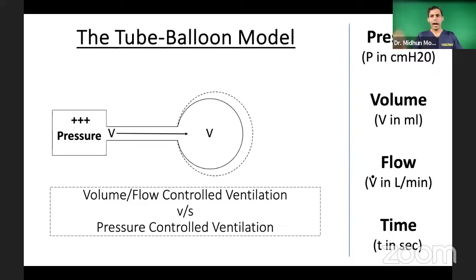So what can I do? I will increase the pressure setting in the ventilator. I make it around 20. Now I'm seeing that the patient is getting around 500 ml of tidal volume. So what I am setting here, what I am controlling here, is the pressure. What is not under my control is the volume. So this is called pressure controlled ventilation. In any ventilator, you can choose either volume control or pressure control, but never both at the same time. And this is a basic concept only, right?